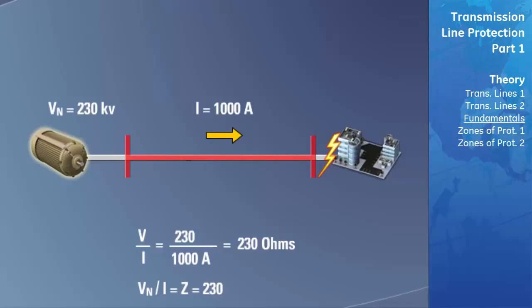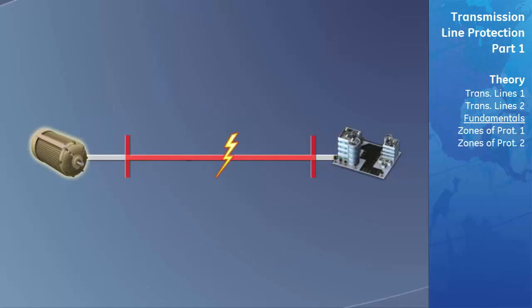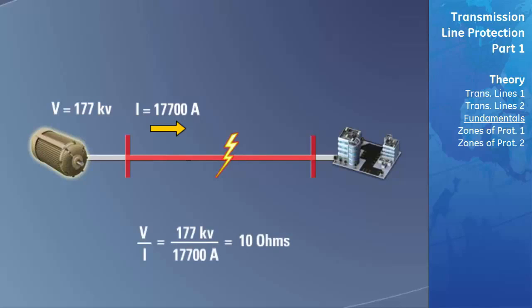The voltage will decrease because the only voltage drops now occur across the transmission line and the source impedance. In this example, the fault is located after the transmission line but before the majority of the power system load, so the only impedance is that of the source and the transmission lines before the fault. Distance relays are programmed to know the impedance to the end of the transmission line. If the impedance the relay calculates is less than the impedance of the transmission line, the relay knows that the fault is on the transmission line itself and must trip the circuit. By comparing the calculated impedance with the known impedance, you can determine how far along the transmission line the fault occurred, leading to the term distance relaying.